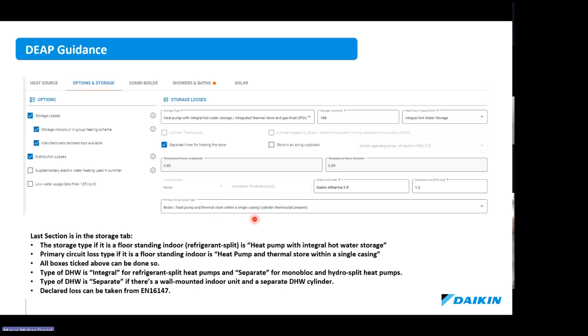And then next is your multiple heat pumps in dwelling. So if you have multiple heat pumps in a dwelling, you need to complete this Excel tool, which is the DEAP heat pump calculator tool. And you have 3 tabs in total. One is your basic input tab, and then your HP1, HP2, and an HP3 tab as well if you have 3 heat pumps. So you're entering all of your ecodesign data in your HP1, HP2. You need to enter the percentage of your heating system, so if it's 100% for domestic hot water for HP1, or 50-50 for HP1 and 2. So you have that option to select, and the tool automatically calculates the heating efficiency in this case.